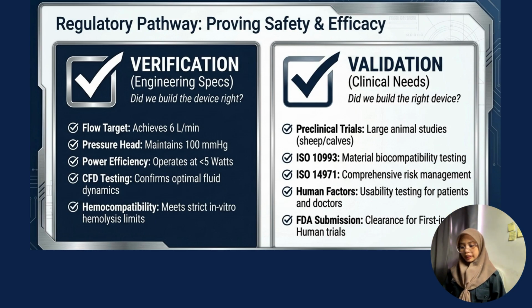Secondly is the pressure head, where we are able to maintain 100 millimeter mercury, showing that it can generate sufficient pressure to support systemic blood circulation. The device operated below 5 watts, indicating good energy efficiency and reduced heat generation. As for the computational fluid dynamics or CFD testing, it was used to optimize the fluid flow inside the pump and minimize turbulence or stagnation zones.